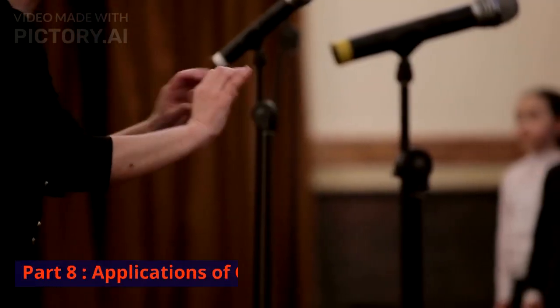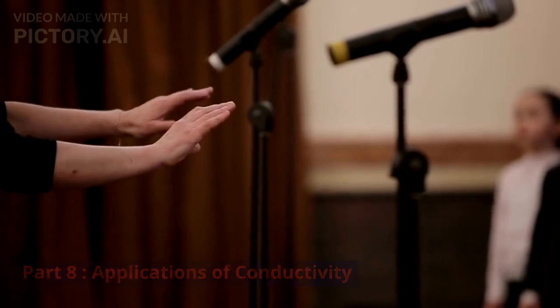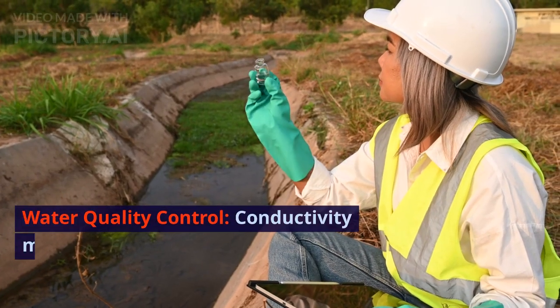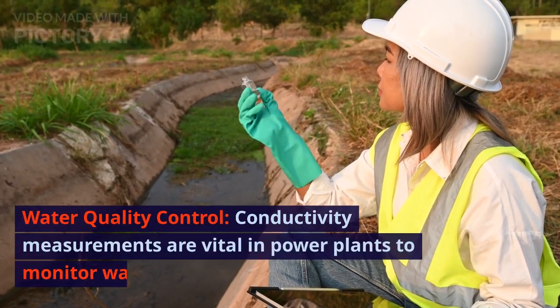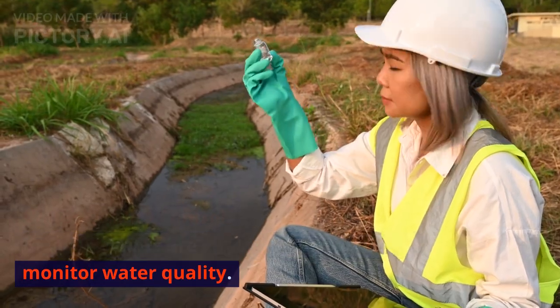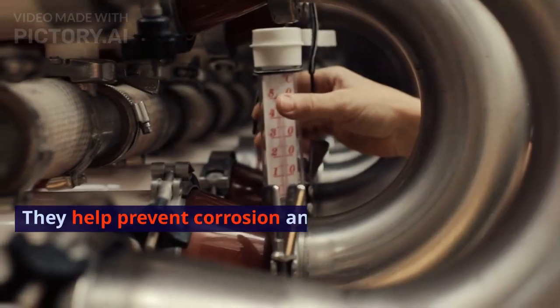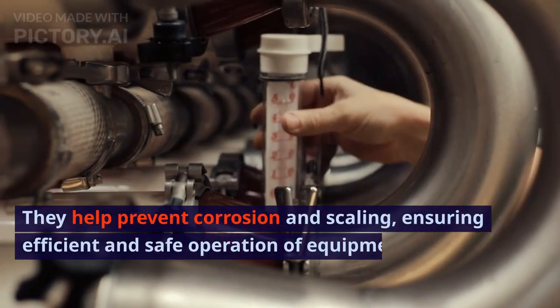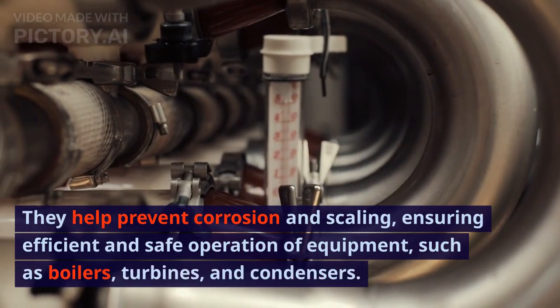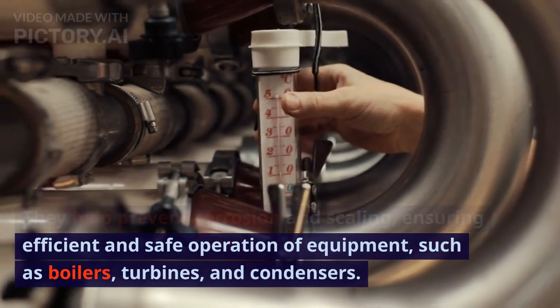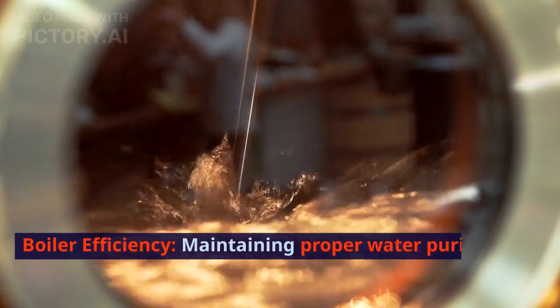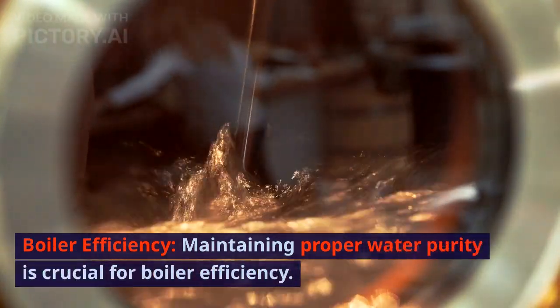Part 8. Applications of conductivity. Water quality control. Conductivity measurements are vital in power plants to monitor water quality. They help prevent corrosion and scaling, ensuring efficient and safe operation of equipment, such as boilers, turbines, and condensers. Boiler efficiency.